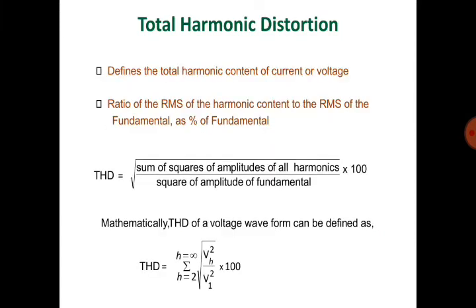Total Harmonic Distortion (THD) defines the total harmonic content of the current or voltage. It is the ratio of the RMS of the harmonic content to the RMS of the fundamental, expressed as a percentage. THD equals the square root of the sum of squares of the amplitudes of all harmonics, divided by the square of the amplitude of the fundamental, multiplied by 100. Mathematically, THD = √(Σ Vh² from h=2 to ∞) / V1 × 100.